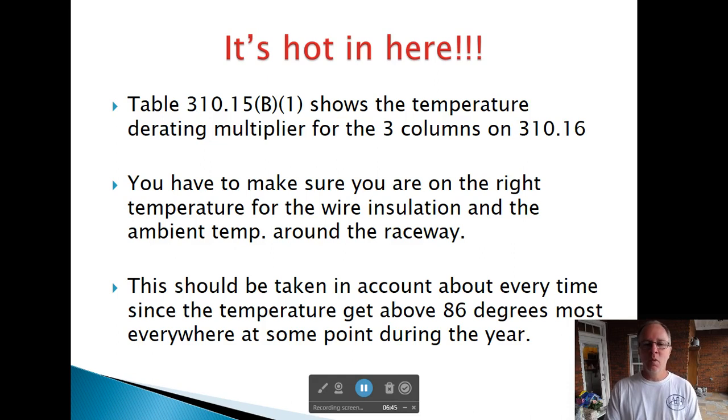It's hot in here. What if we're in Alaska on a roof in the day of winter and it's 10 degrees? If we're trying to dissipate heat, I feel like that wire could dissipate heat pretty well because it's in a cold atmosphere. What if we're in sunny South Florida on a roof in the middle of July? Will that wire be able to dissipate the heat as well? I'm going to say it won't. And so that's where we're adjusting on this table—the ambient temperature surrounding it.